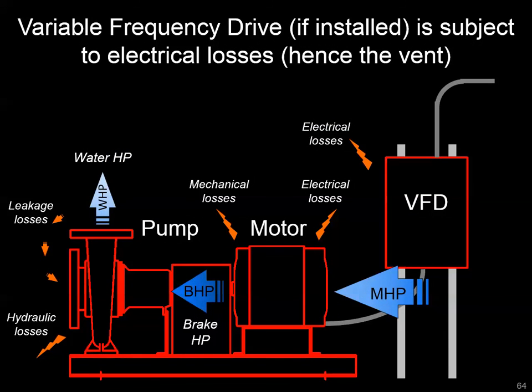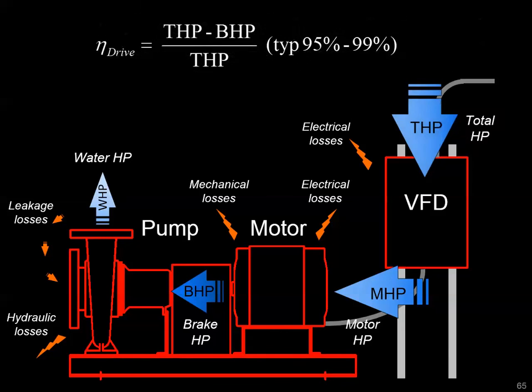If you have a variable frequency drive (VFD), that introduces its own inefficiencies. It's a piece of electronics that consumes power, and the vent on the side of the VFD cabinet is indicative of the heat losses from these components. It may only be a couple of percentage points, but when considering installing a VFD, make sure the economics bear out — that you'll be varying or trimming the pump operation enough to justify those efficiency losses.